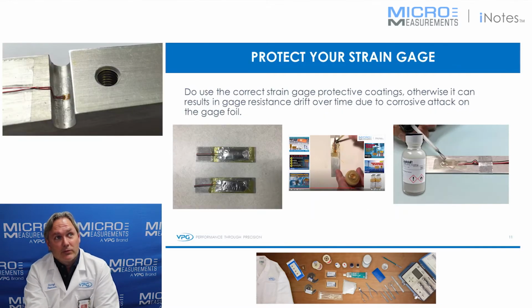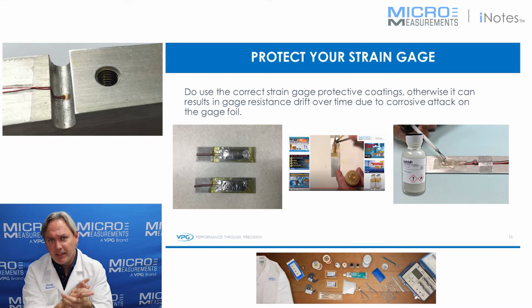Do use the correct strain gauge protective coatings, otherwise it can result in gauge resistance drift over time due to a corrosive attack on the gauge foil. Sometimes we'll have customers that go find coating systems that they use for other things. It may be like a potting compound. It may be something that's an automotive material that now they're trying to use with strain gauges.